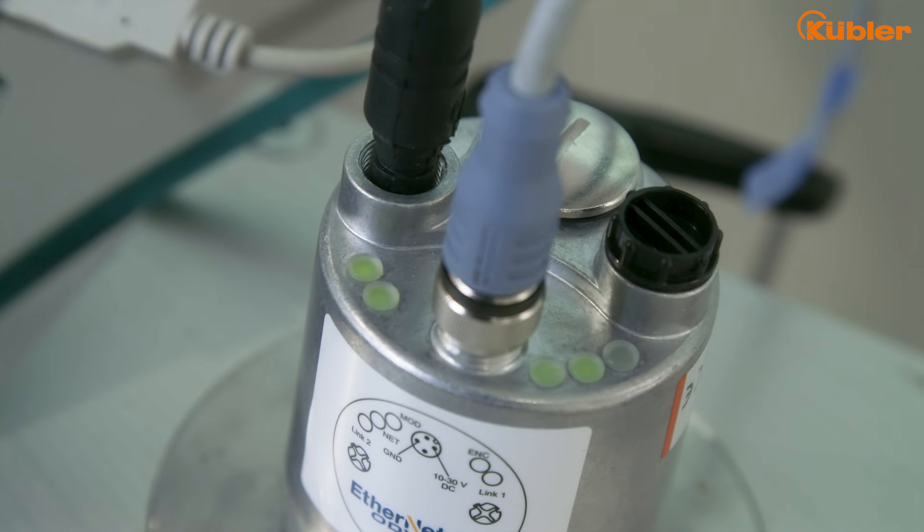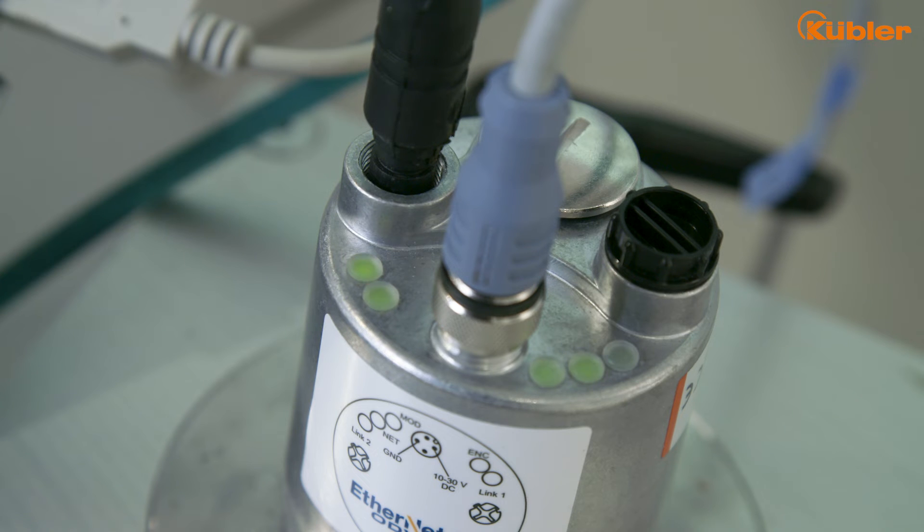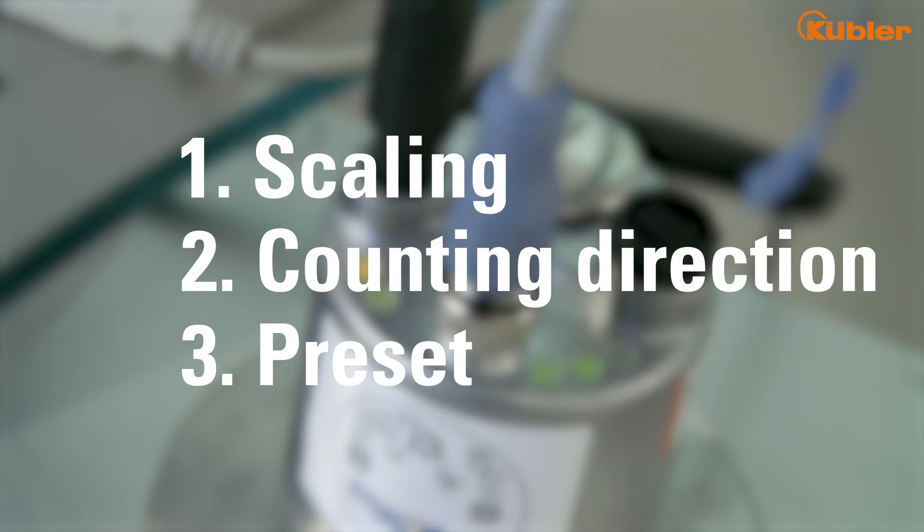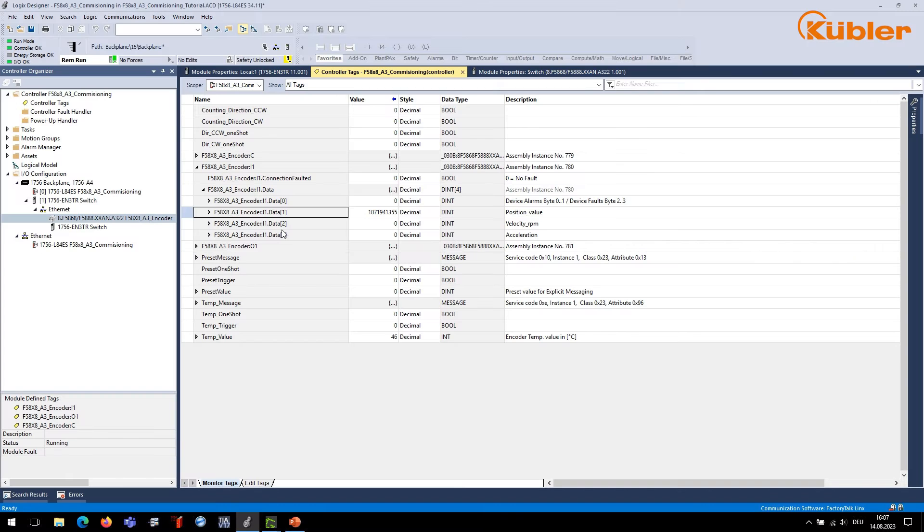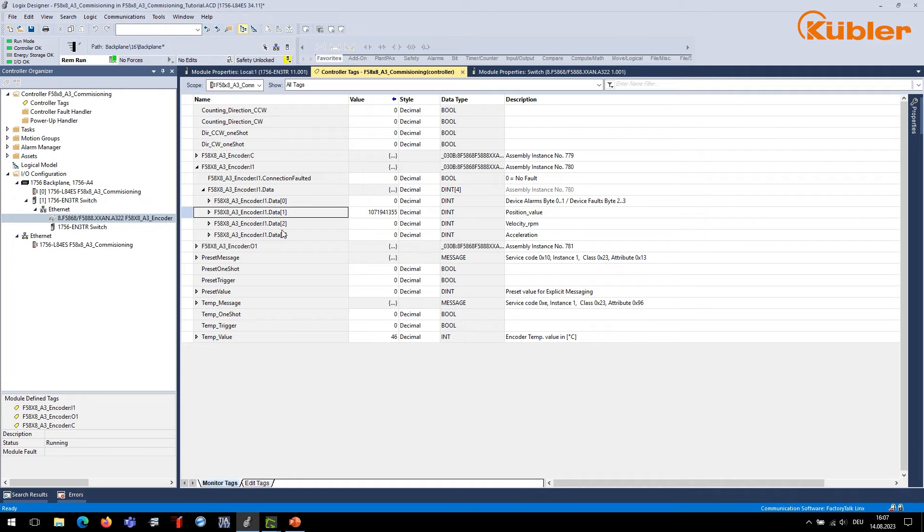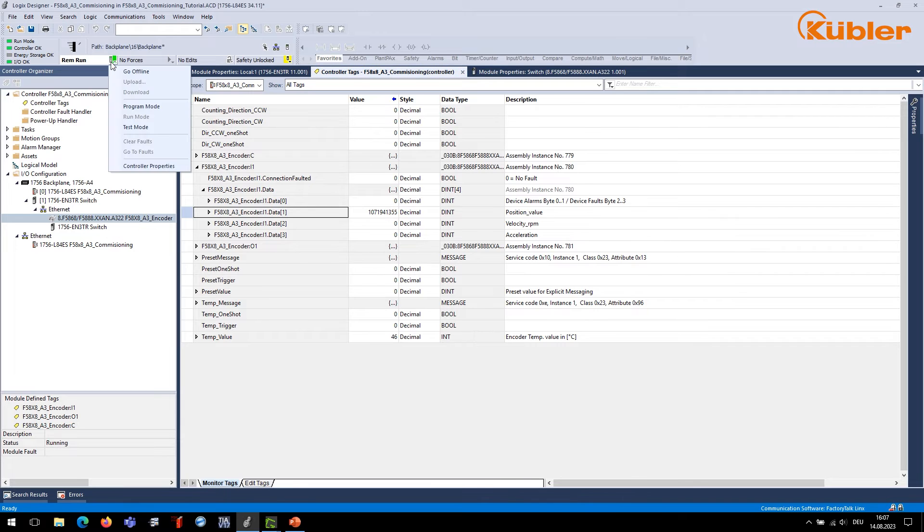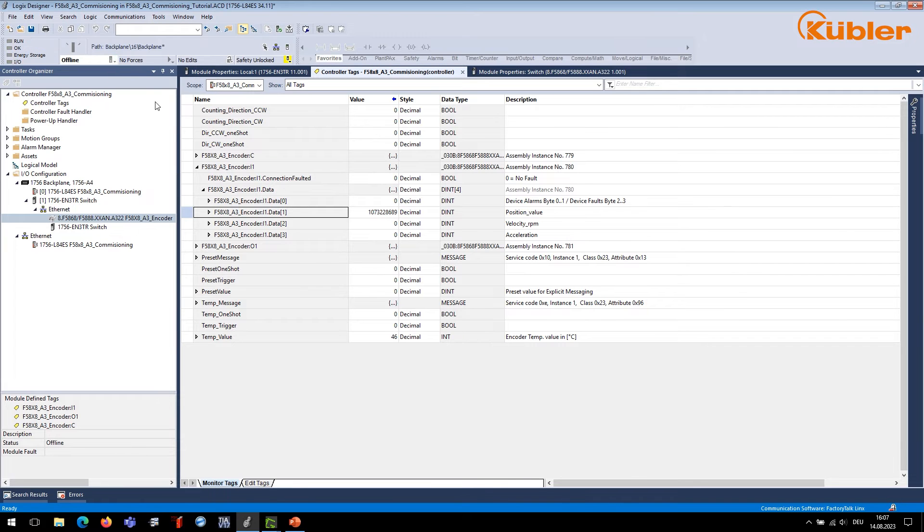Now that the encoder is working, we can configure its parameters. We will see how to adapt the scaling, the counting direction, and how to do a preset. For standard configuration, you would use the configuration parameters of the configuration assembly. These parameters are only sent acyclically at the start of the connection, so first you have to make sure that the connection state is offline.